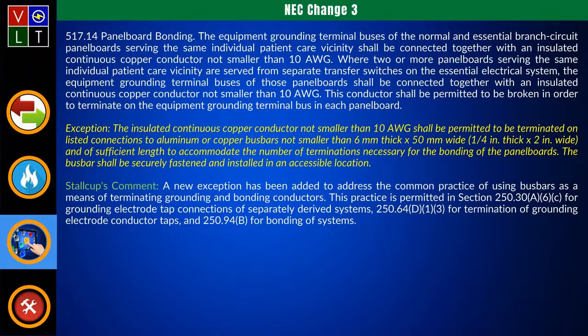If you look at 250.30A6C for grounding electrode tap conductors dealing with separately derived circuits, this type of practice is permitted there. And if you look at 250.64D13 for terminating grounding electrode taps, and 250.94B for bonding of systems, you'll see they're already doing this. Now they're just allowing you to do what's already done in Article 250, over here in a healthcare facility.